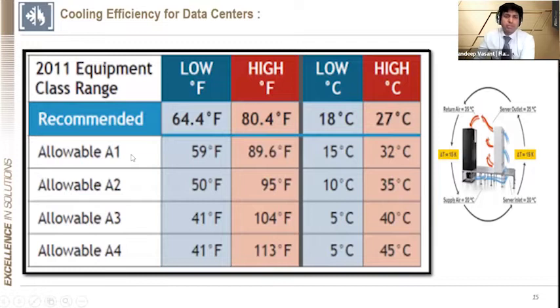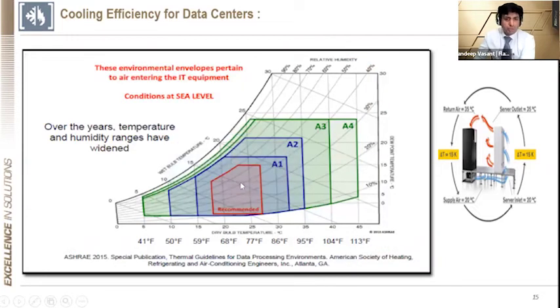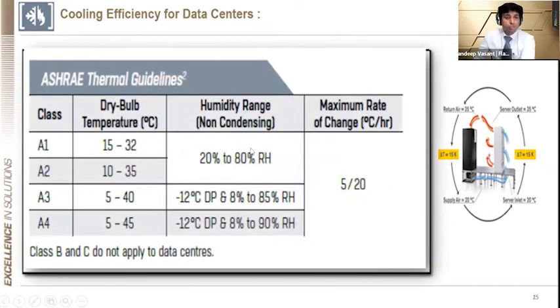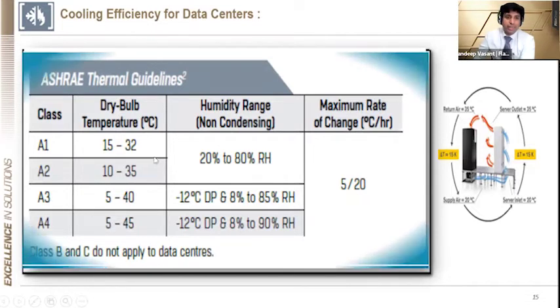The next very important thing is the ASHRAE 2011-15 and the TC 9.9 document, which says to operate the cooling units in the data center between the gradient of 18 to 27. Here is the PAC, here is the rack. The supply air temperature I am talking about here is between 18 to 27, and the hot air goes back to the unit. So there are clearly defined ASHRAE documents which say recommended A1, A2 and A3, A4 depending upon the type of server. I'm happy to see most of the data center end users and IT customers are sharing with us the A1, A2, A3 and A4 gradient, thereby helping us to design the right PAC unit.